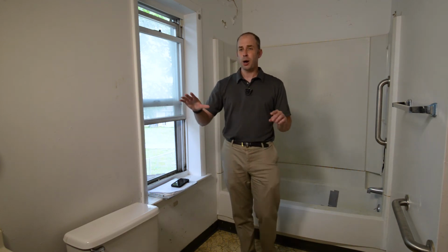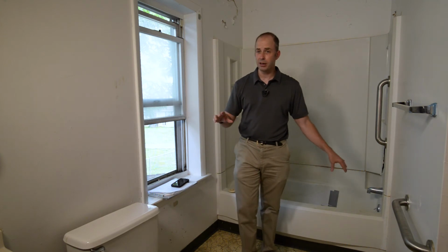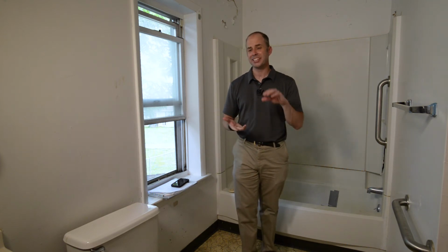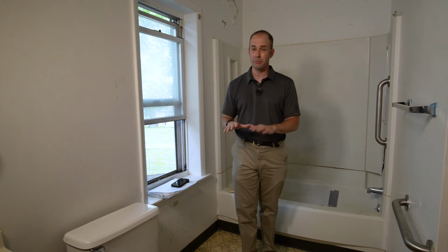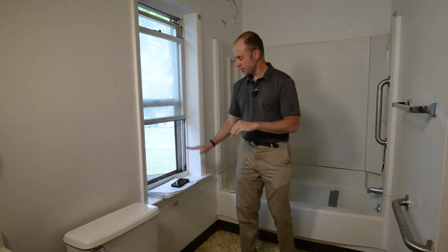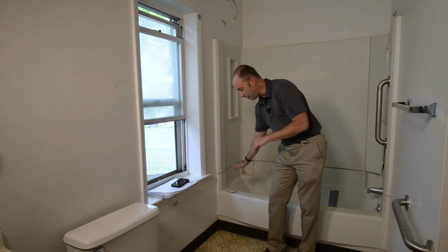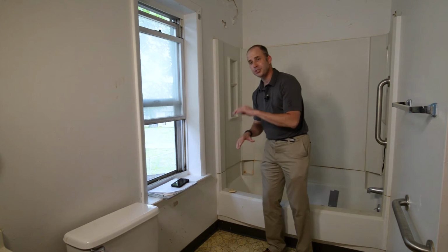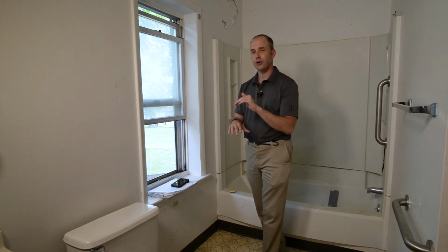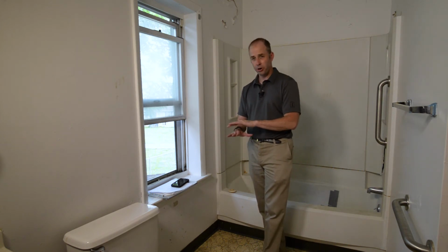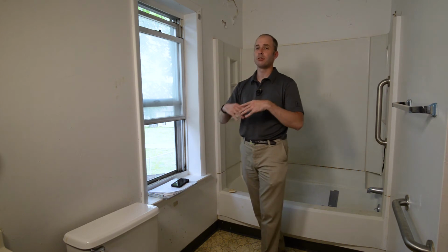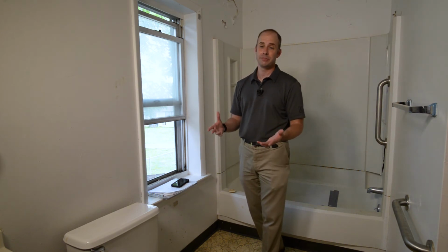Also with the faucets, while we're looking at those, particularly with the tub, it's more common where we come across that it has to be above the flood level rim of a tub. What do I mean by over the flood level rim of the tub? So essentially, if I have the rim of my tub here, the faucet has to be above this level. That is to create an air gap between the faucet and the level of the water in the tub. That is to prevent any type of contamination of the system.